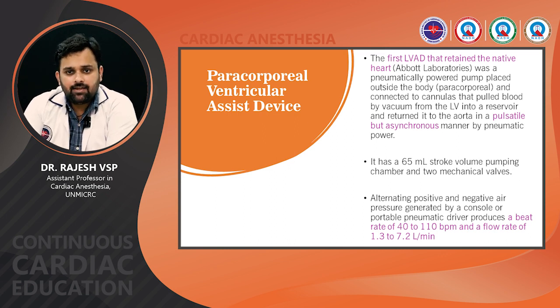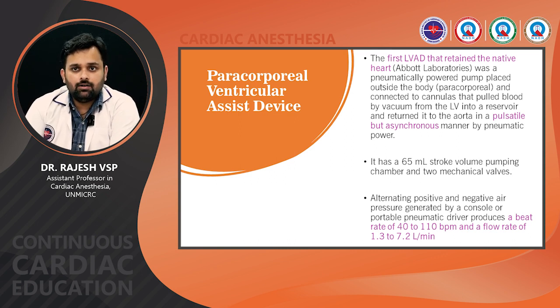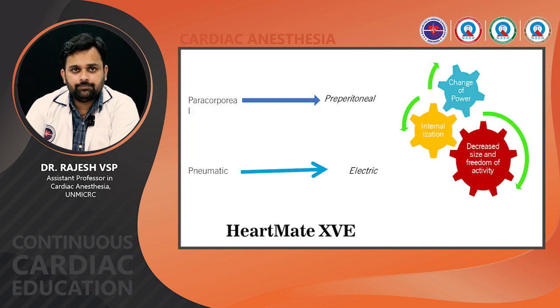It has a 65 ml stroke volume pumping chamber and 2 mechanical valves. Alternating positive and negative air pressure generated by a console or portable pneumatic driver produces a beat rate of 40 to 110 beats per minute and a flow rate of 1.3 to 7.2 liters per minute.